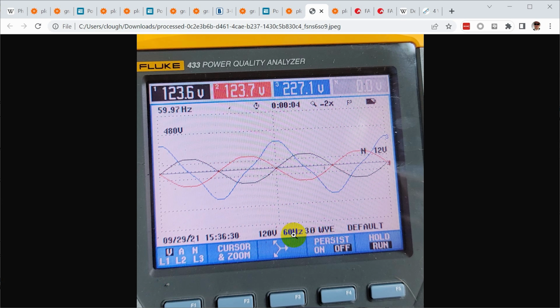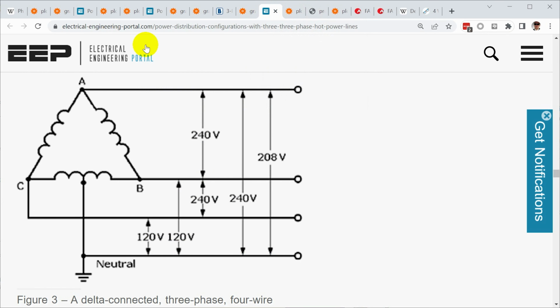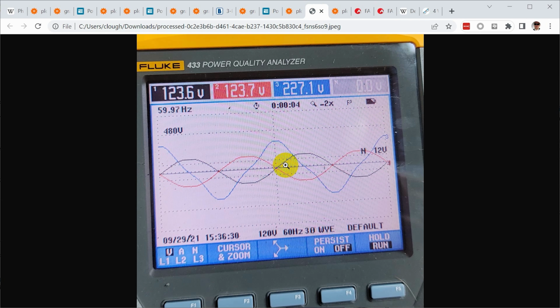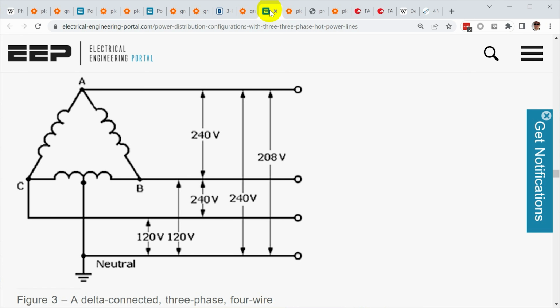You've got the two phases, and you've got the third that's generated at 90 degrees between them. But there's a clue right down here at the bottom of what's going on. He's got this configured for three-phase Y, but we're not looking at a three-phase Y system. We're looking at a high leg delta configuration. So what's happening is it's measuring this waveform with respect to neutral. Well, what happens if you instead ignore the neutral and just measure from A to B, from B to C, and from C to A?